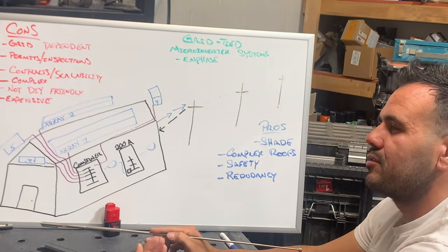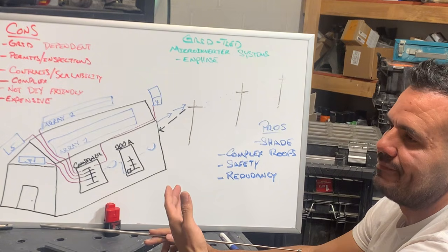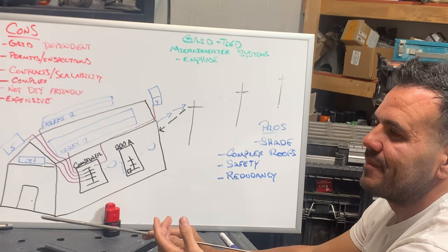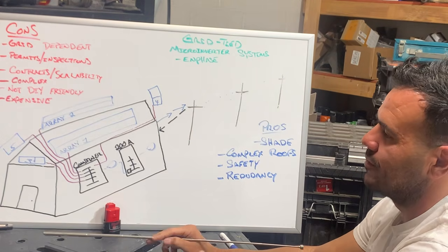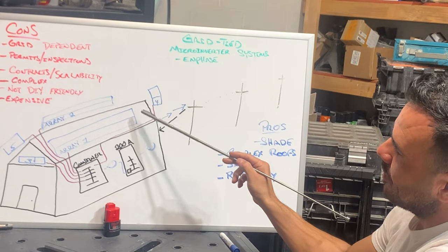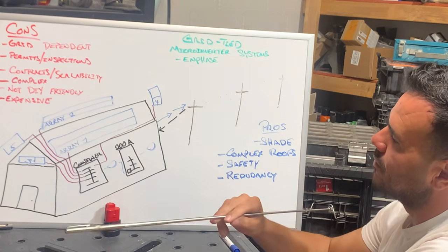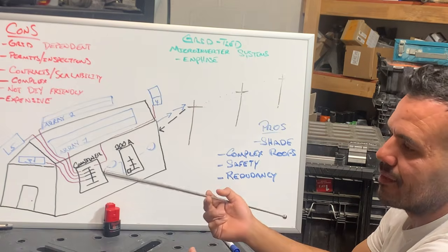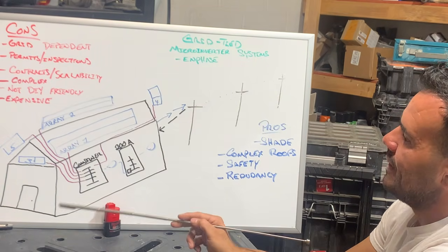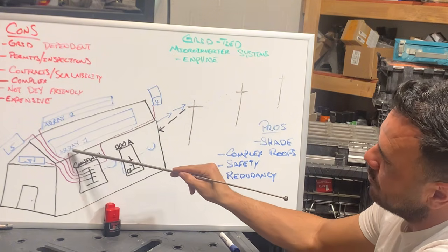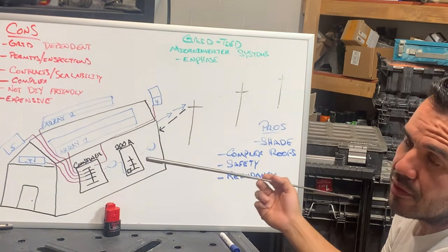We'll say that each solar panel had a VOC of 40 volts, and the amperage was, we'll say, 10 amps. So 40 volts, and we had 10 solar panels. If we hooked up our 10 solar panels in series, we'd have approximately 400 volts and 10 amps. And so on the string leaving the array, we would have 400 volts and 10 amps going to our inverter.